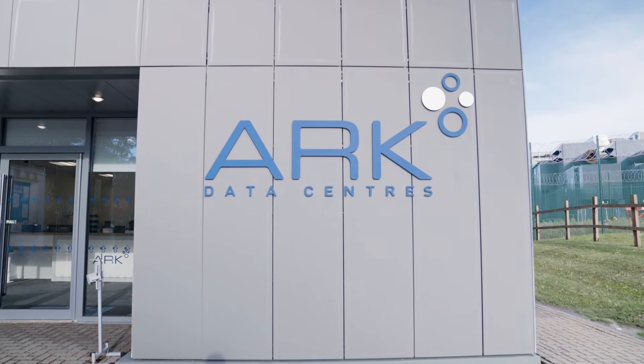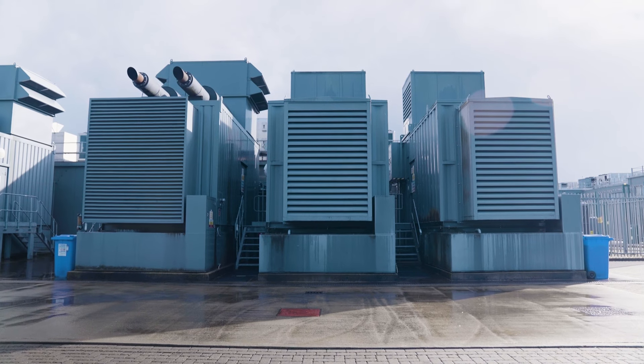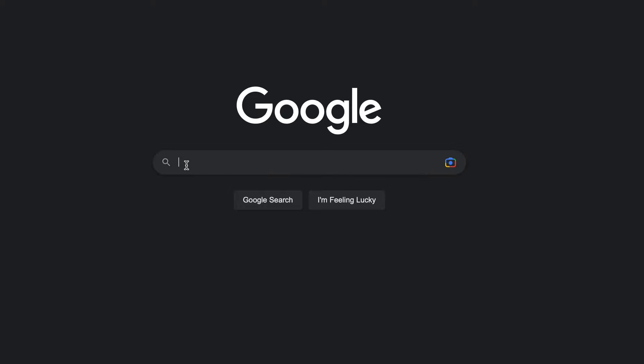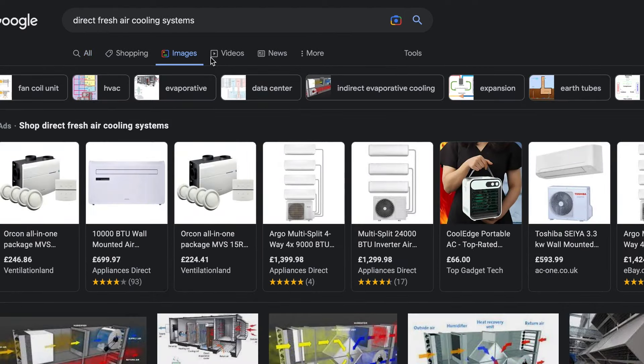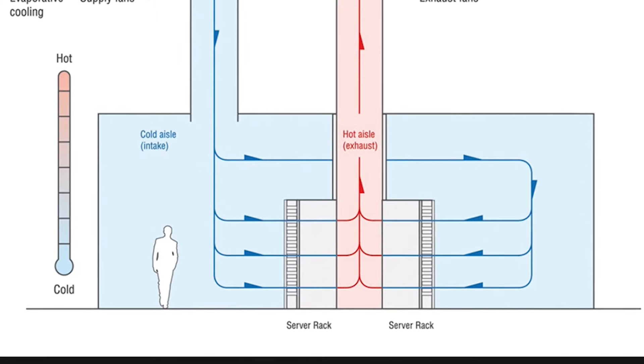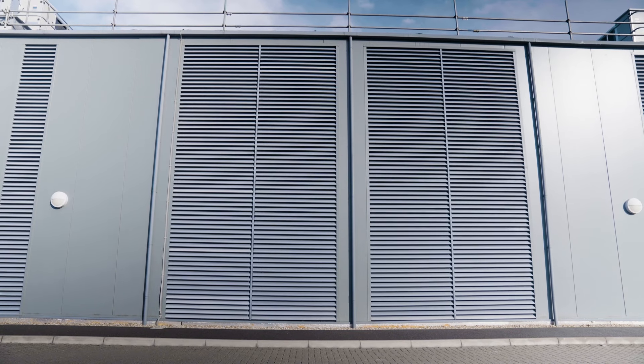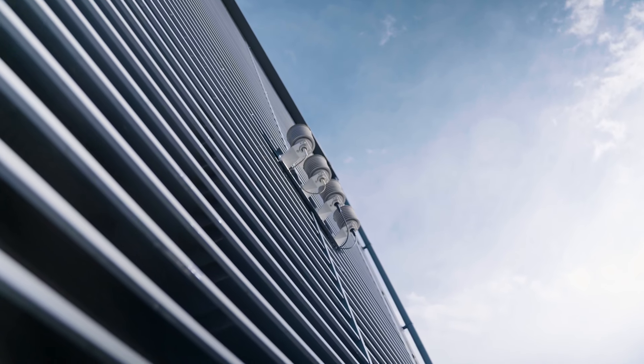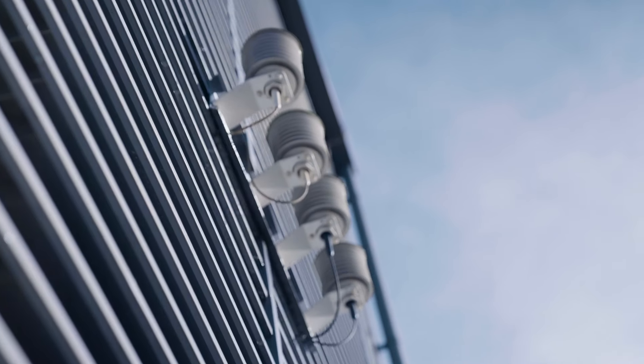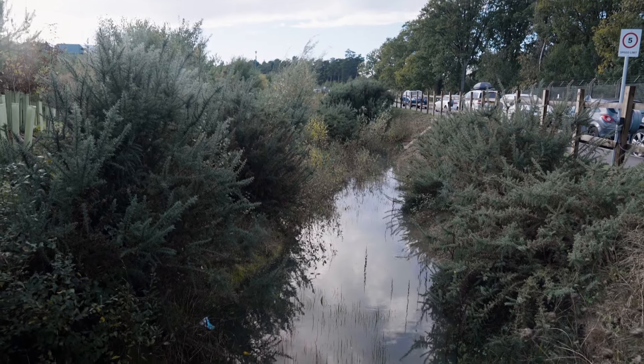When we started at Ark, we really focused on the energy side of things, because energy efficiency was where we were going to make our unique selling point. We started with direct fresh air cooling systems deployed en masse, because that was a way of reducing the energy load on the data center — from where more than 50% of the energy consumed was for the cooling system, to where we are now at about 6%.